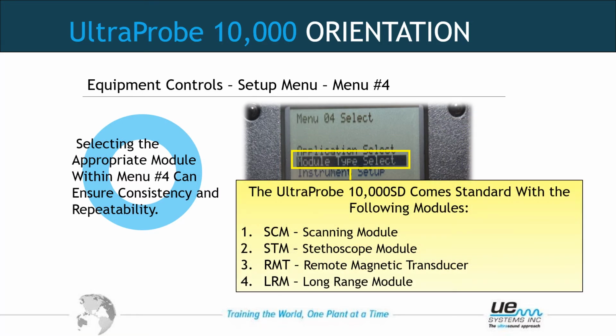Once we exit back out to the main menu, you have module type select as number 4. Some of the common modules listed in here are SCM is scanning module, STM is stethoscope module, RMT is the remote magnetic transducer, LRM is the long range module. In the instruction manual for the instrument, as well as the DMS software, all these abbreviations, there are many more, are listed out as to what they are. It's important to keep up when trending or trying to be repeatable that we keep up with what module was used on the routes.